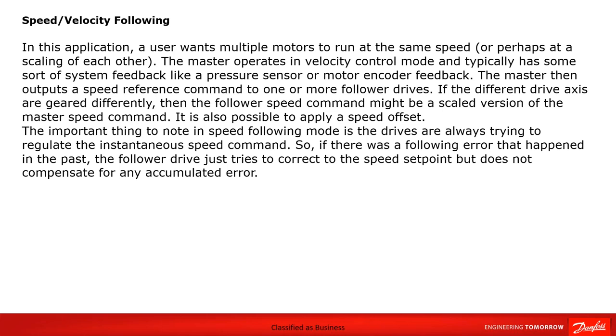But the important thing to note in speed following mode is that the drives are always trying to regulate the instantaneous speed command. So if there was a following error in the past, the follower drive just tries to correct to the speed set point, but doesn't compensate for any accumulated error.